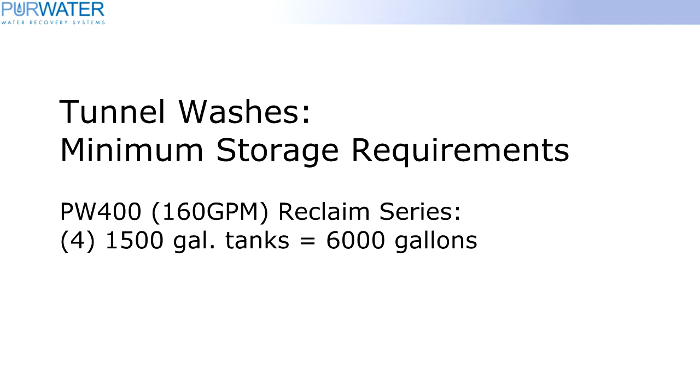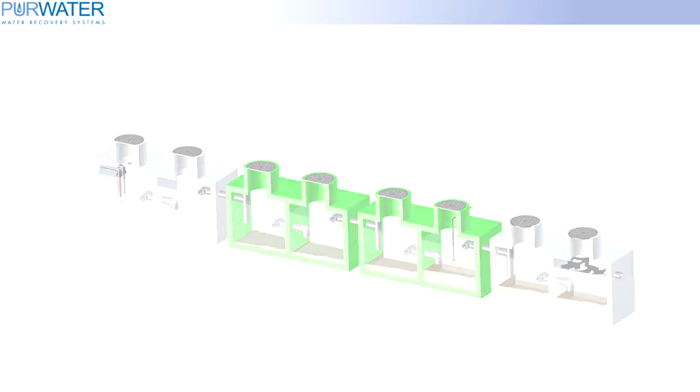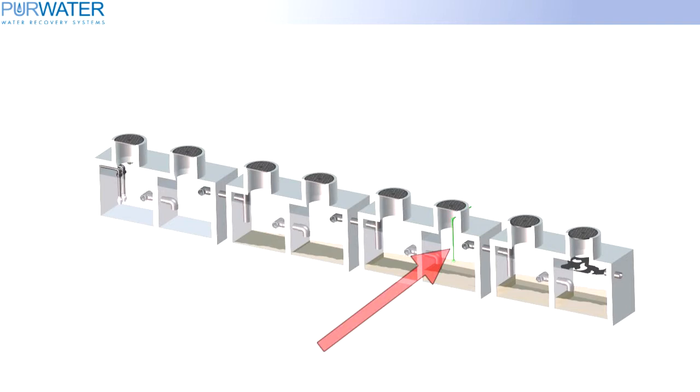In a tunnel wash using a PW400, a minimum of 6,000 gallons is required. When using four tanks, you would have two tanks added in the middle of a two-tank setup. In this case, the only plumbing change would require the recirculation line to be plumbed into the second tank, first chamber.